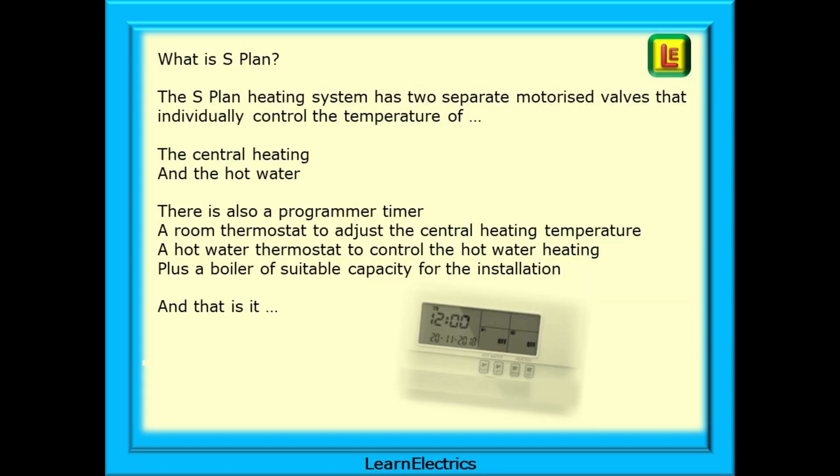So what is S-Plan? As you will see, the S-Plan heating system has two separate motorized valves that individually control the temperature of the central heating and the hot water. There is also a programmer and timer to set the on and off periods. A room thermostat is used to control the central heating temperature and a hot water thermostat will control the hot water heating.